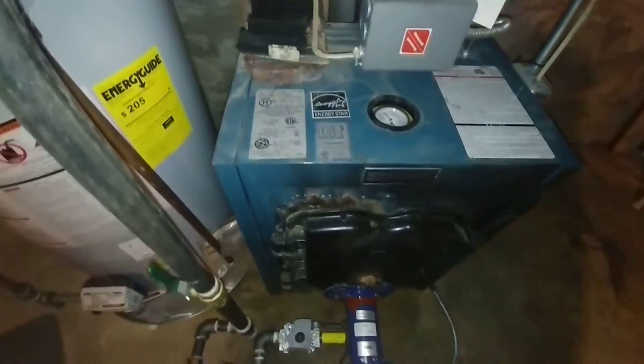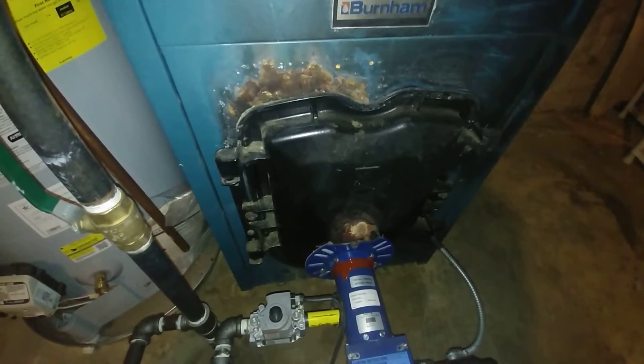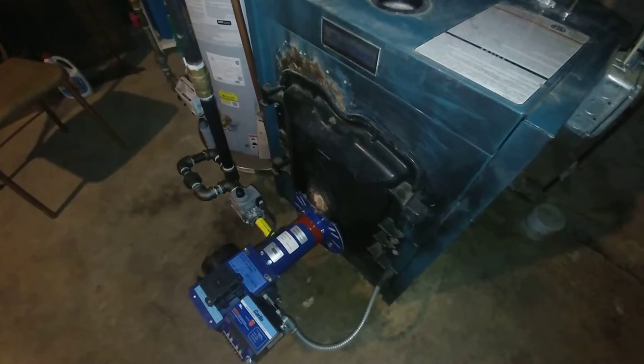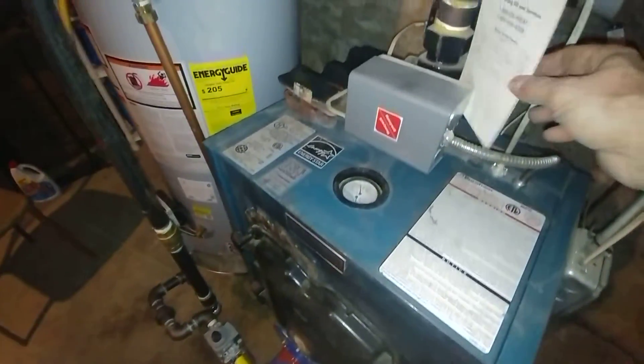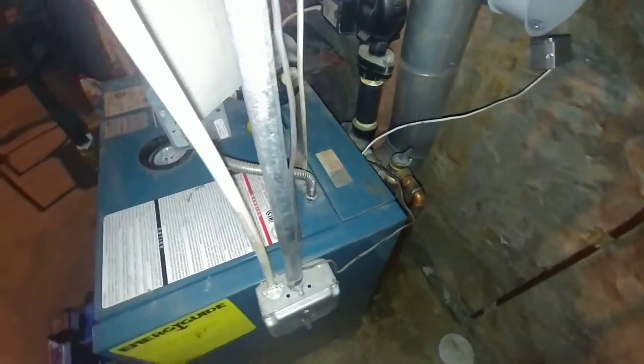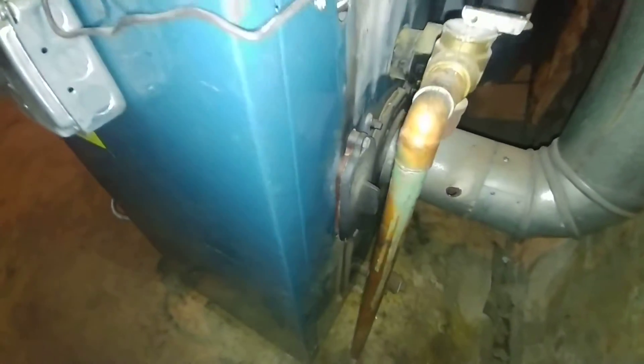Right now we wanted to make sure that we had enough flue gas temperatures to stay in vapor form all the way out. The oil company, which shall remain nameless, installed this and has not been maintaining it properly, and so they've pretty much lost this customer. Otherwise it's a really good boiler.